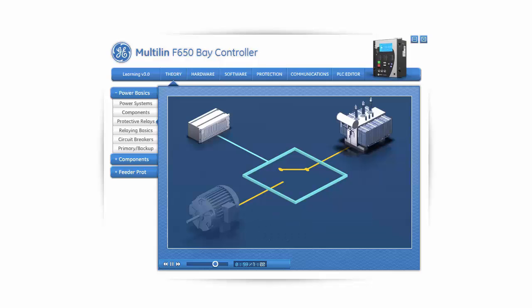The protective relay uses current and voltage instrument transformers to acquire information about the system, such that a fault can be located. The type and location of the instrument transformers, the circuit breaker which is to be tripped by the protective relay when it operates, and the signal level required to operate the relay are selected when the relay is applied to the power system.